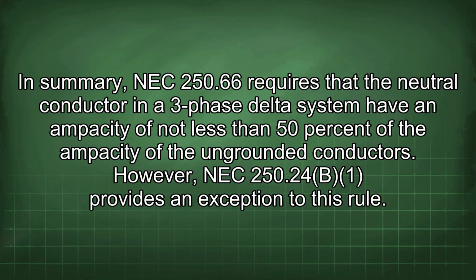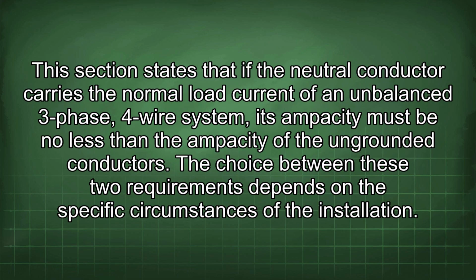In summary, NEC 250.66 requires that the neutral conductor in a three-phase delta system have an ampacity of not less than 50% of the ampacity of the ungrounded conductors. However, NEC 250.24(B)(1) provides an exception to this rule. This section states that if the neutral conductor carries the normal load current of an unbalanced three-phase, four-wire system, its ampacity must be no less than the ampacity of the ungrounded conductors.